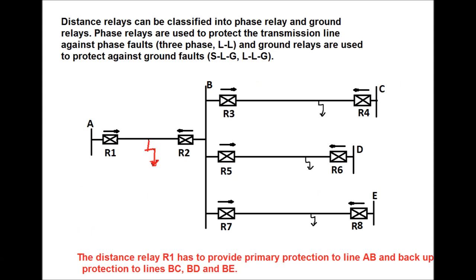Distance relays can be classified into phase relays and ground relays. Distance relay has both features for phase fault and ground fault. Phase relays are used to protect the transmission line against phase faults such as three-phase or double line faults. Ground relays are used to protect against ground faults such as single line-to-ground fault and double line-to-ground fault. In this figure, A is the substation from which a line goes to substation B. From B, lines go to substations C, D, and E.